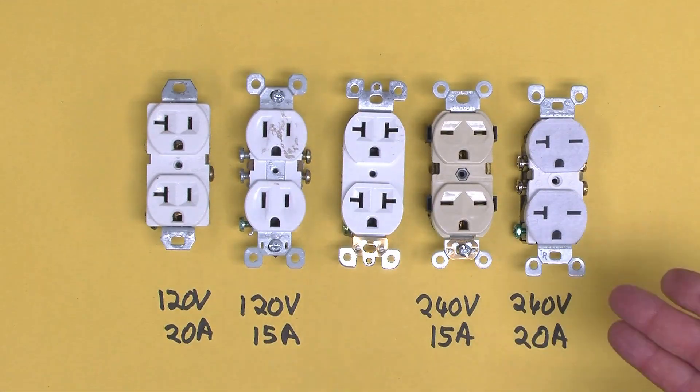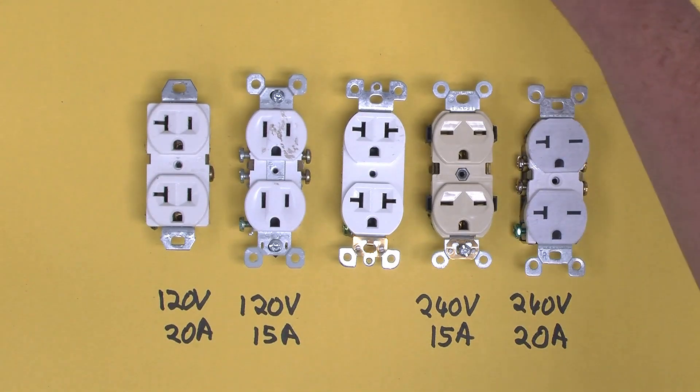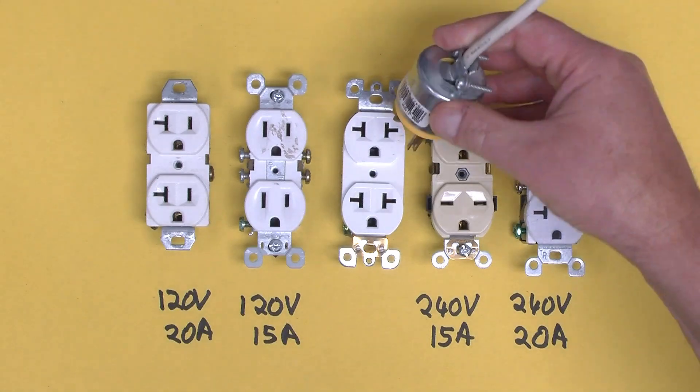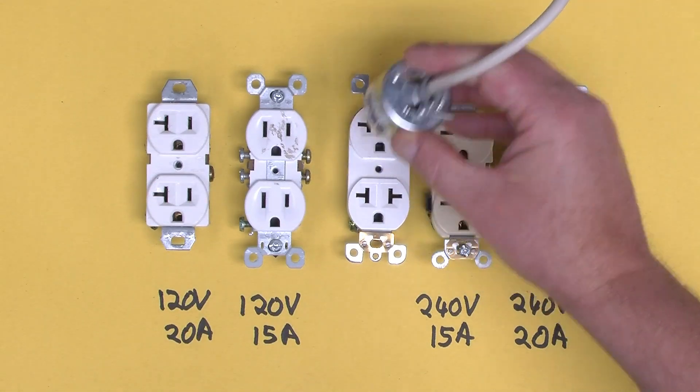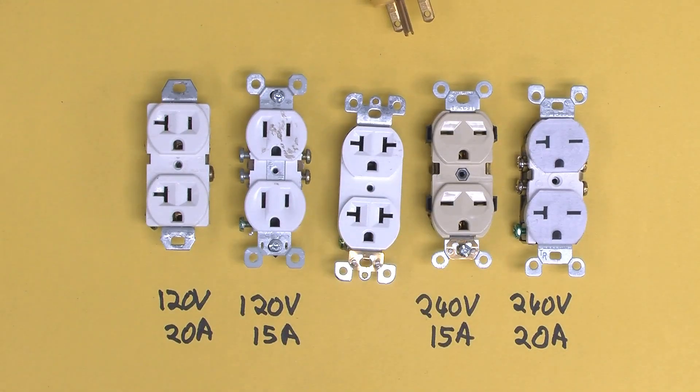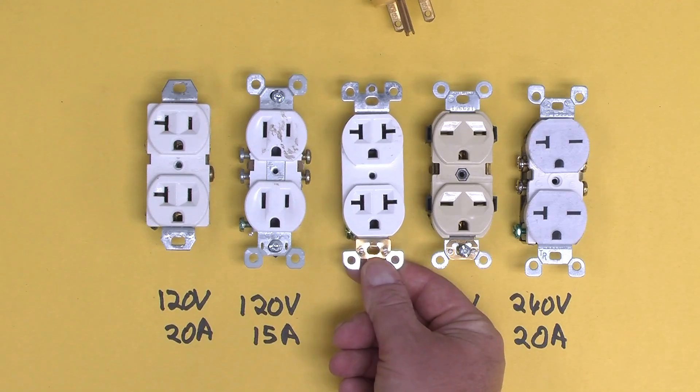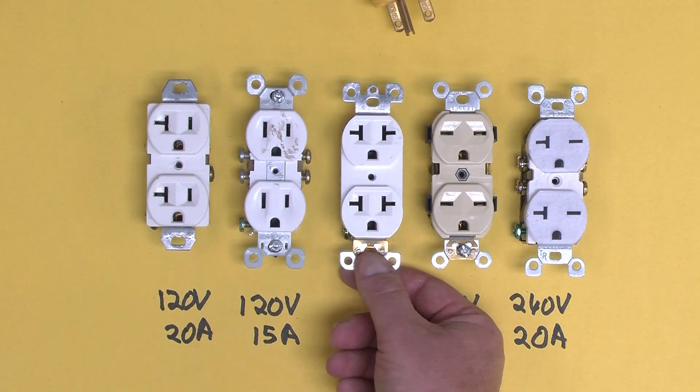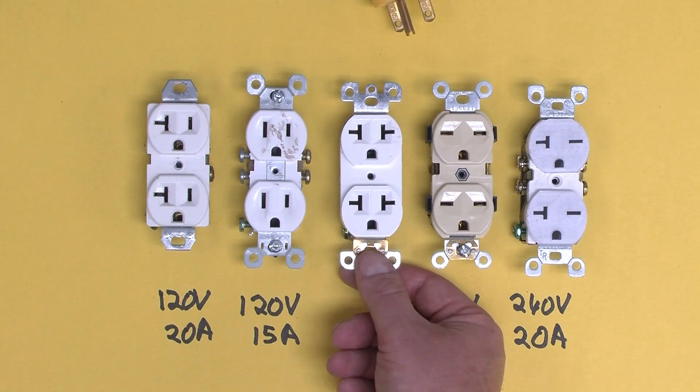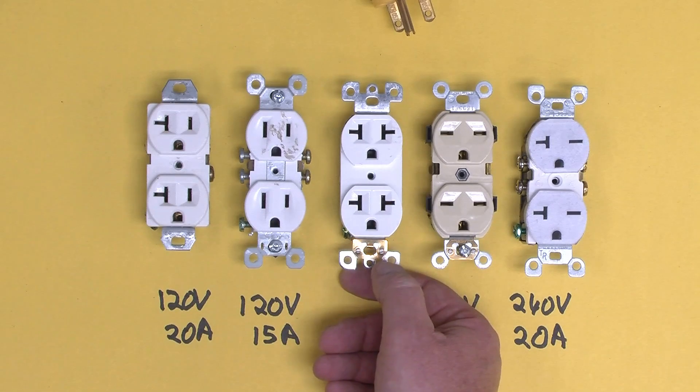Similarly, if you happen to have this set up at 115 or 120 volts and you took your 240 volt appliance and plugged it in, bad things could happen too. Light bulbs will just dim, but motors can actually burn out because they'll draw more current trying to desperately get enough power to come up to speed when they've only got 120 volts available to them.